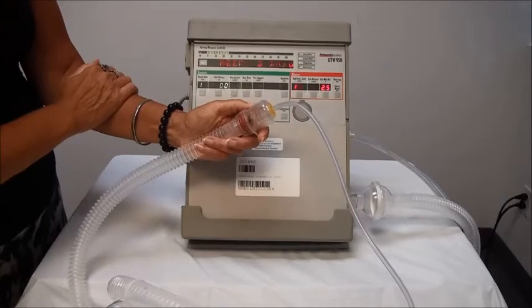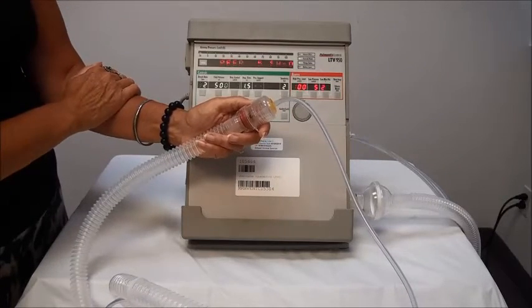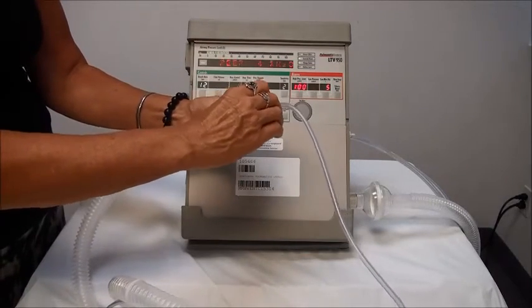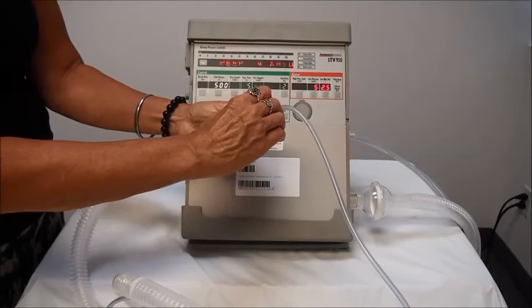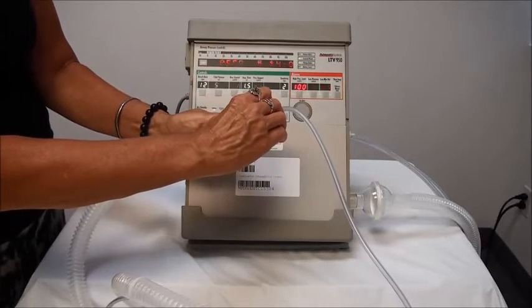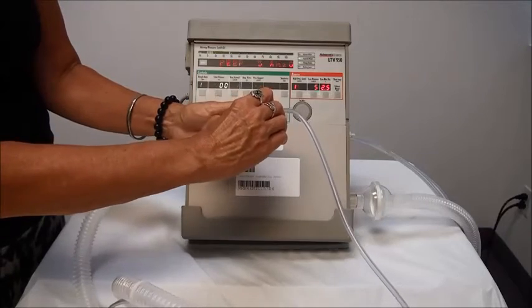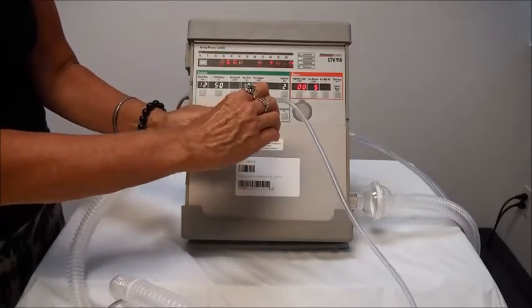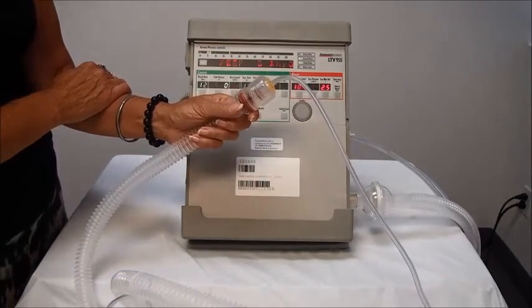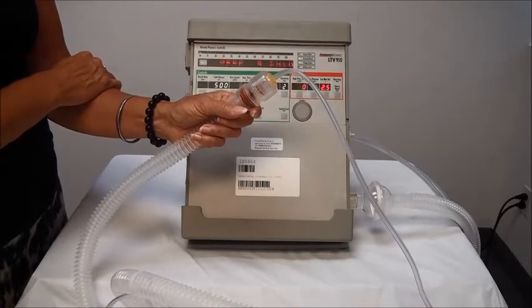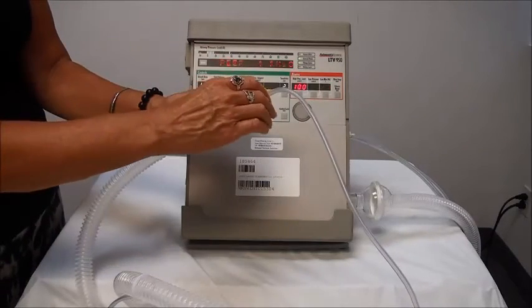So if I want to adjust that lower, what I would do is twist it counterclockwise to set it. Typically 5 is a pretty typical setting of PEEP, but that's not to say that you might not have a different order for a different setting.